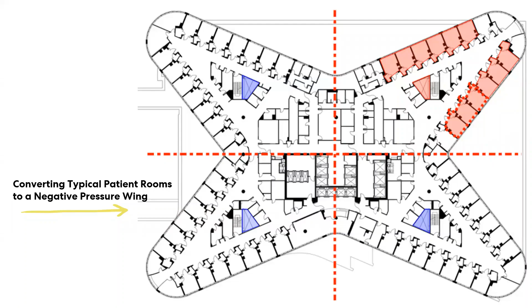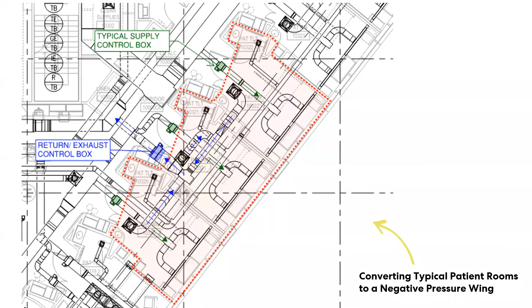As you can see, each of these rooms has the dedicated supply box highlighted in green and a shared exhaust box highlighted in blue. So during normal operation, the supply or green box provides a little bit more air than we're removing from the room for a slightly positive room to keep the room clean. But when we switch to a surge mode, we are able through the building controls to draw more air from those spaces than we supply by increasing the airflow through the exhaust box in blue. That starts to draw air in from the corridors. It makes the patient rooms negative to the spaces that surround it.